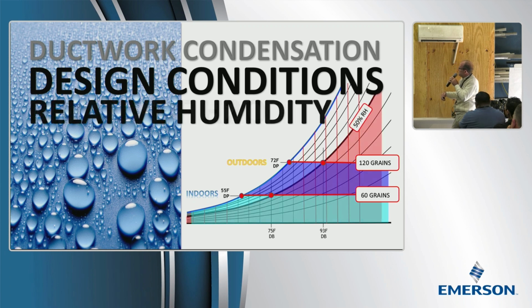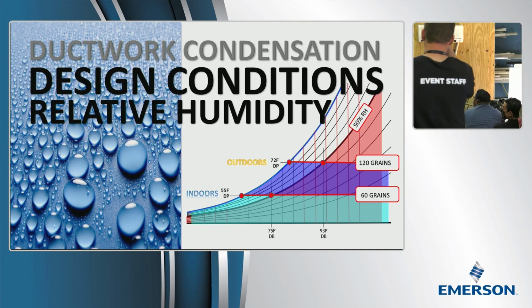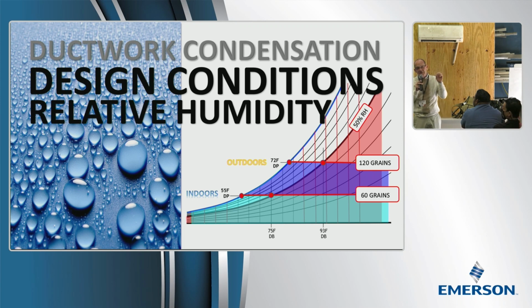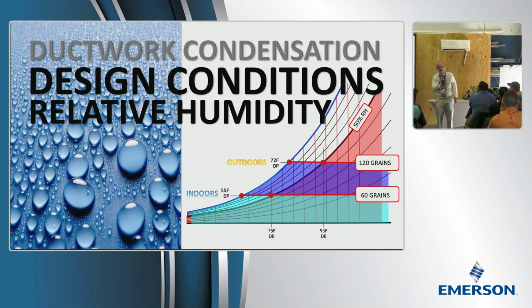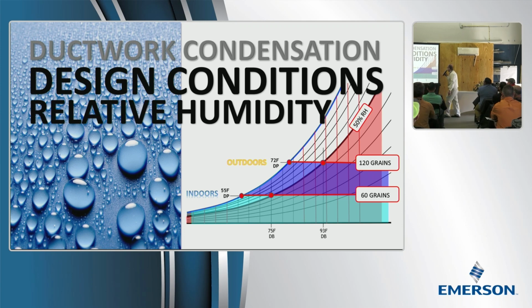The thing I need everybody to understand is that we're at 50% outside and we're at 50% inside, and you have to understand that concept. If you're not in the habit of writing down the temperature that goes with a relative humidity measurement, get in that habit, because relative humidity doesn't mean a thing when you just tell me it's 50%. Customers do it to you too - I got 50%, is that okay? Or the service tech writes down 50%. These are both at 50%.